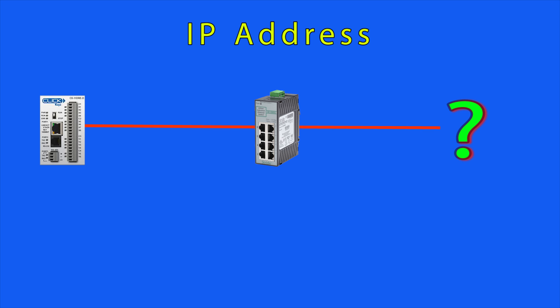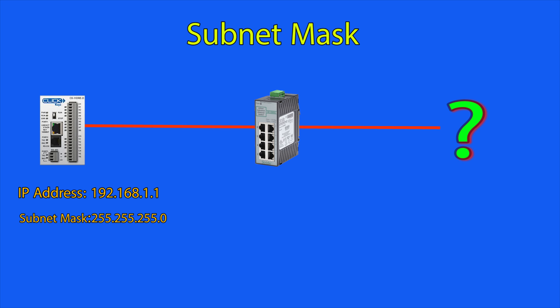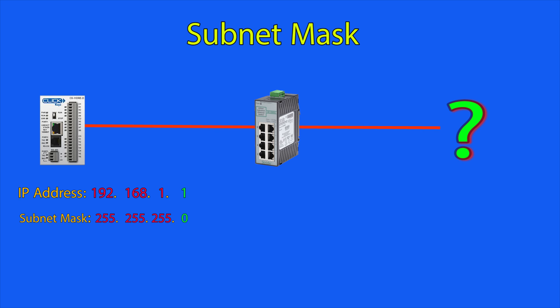How can you determine what this PLC can talk to? This is done by using the IP address along with the subnet mask. The subnet mask is also made up of four number groups, and each number group matches up to the IP address number group to define what it can talk to. If the subnet mask number portion is 255, this means that the IP address number portions must match for communication. When the subnet mask's octet is 0, however, the IP address's number portions can be any valid number in the range.